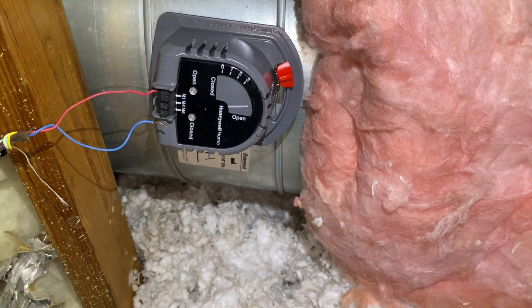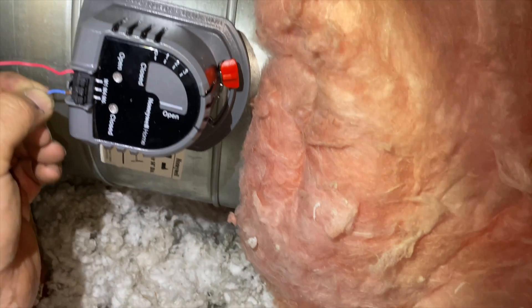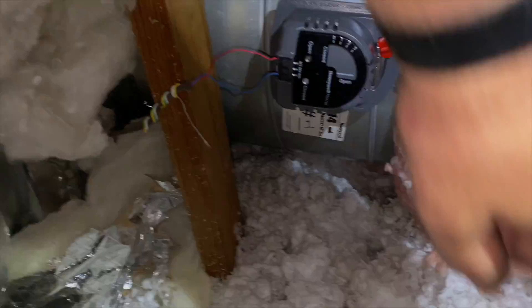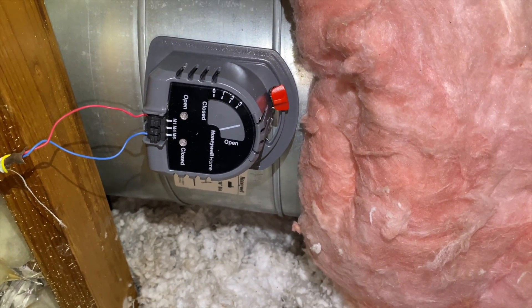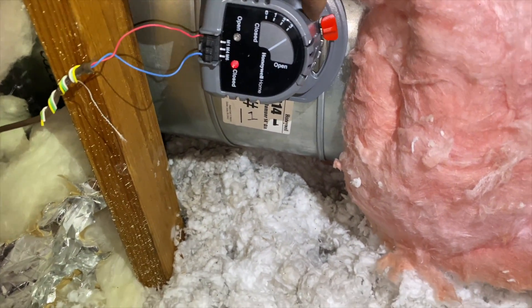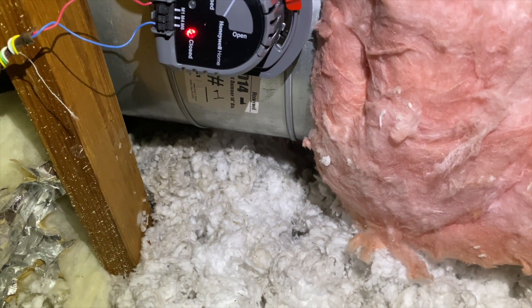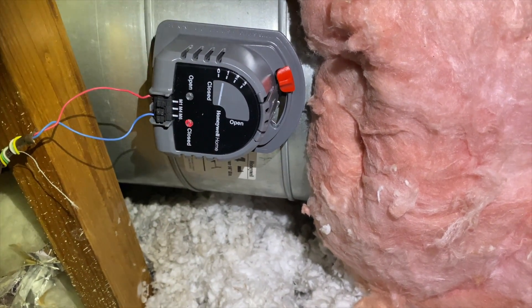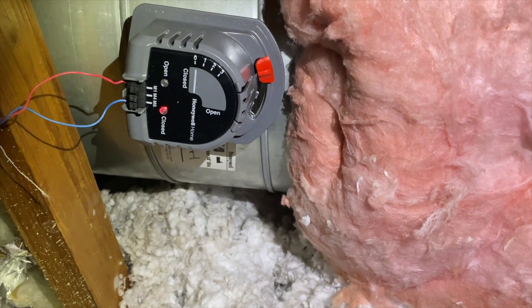Removing power now — as you can see it's springing open. Now closing it all the way again. Looks good — it hits that zero position. If you want to avoid static pressure buildup, you can set these to different presets: zero is all the way closed, one is partially closed, two is a little more open. In this case we're going to zero. There we go — it hit zero completely closed. We've opened it and closed it successfully, so we know it's good.